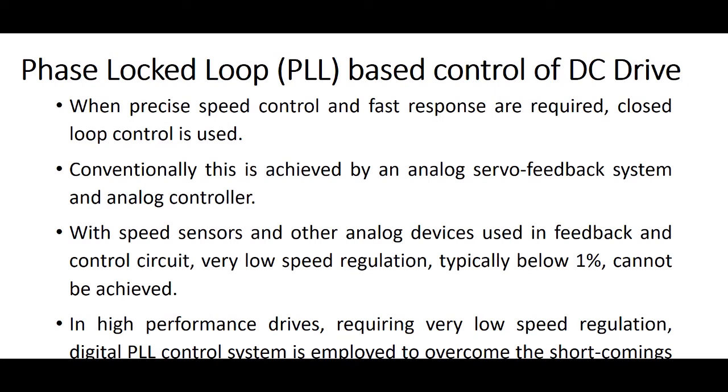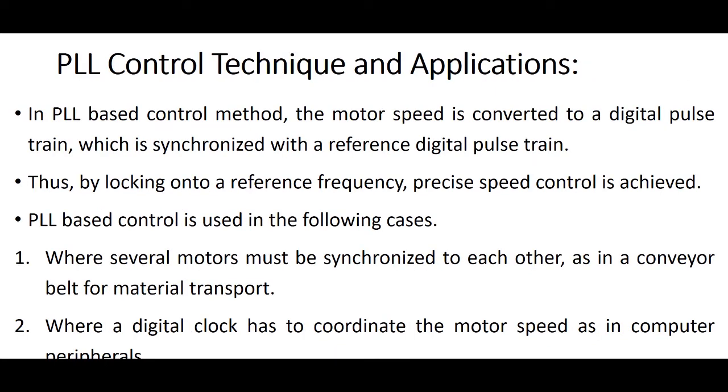In high performance drives requiring very low speed regulation, digital PLL control system is employed to overcome the shortcomings of analog feedback control system. So, what is the PLL control technique and applications? In PLL based control method, the motor speed is converted to a digital pulse train which is synchronized with a reference digital pulse train. Thus, by locking onto a reference frequency, precise speed control can be obtained.